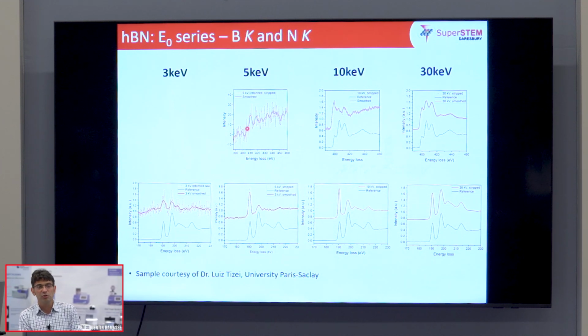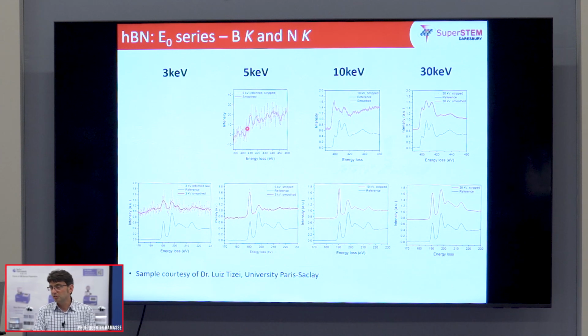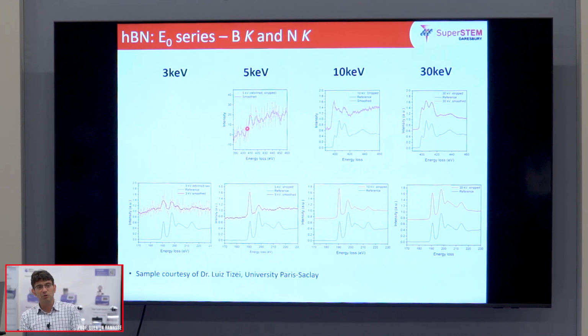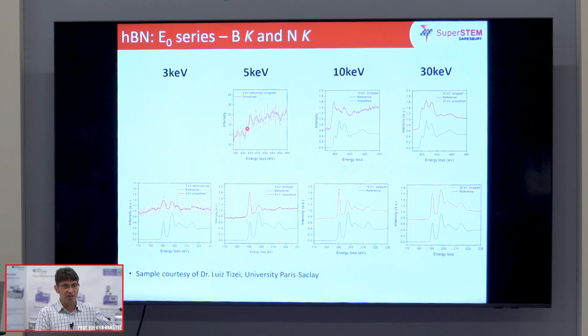So why would you be interested in doing this? Well, many reasons. If you're looking at your sample at 5 kV and you want to do some sort of EELS with it, you don't have to switch, you don't have to go to another machine, it's right there, it's possible, it's alignable. You can do EELS mapping, you have the same resolution, potentially even slightly better resolution because your CC delta E might actually be better at lower kV than at higher kV. You have higher cross sections in EELS at lower kV, so you get a slight boost in signal.